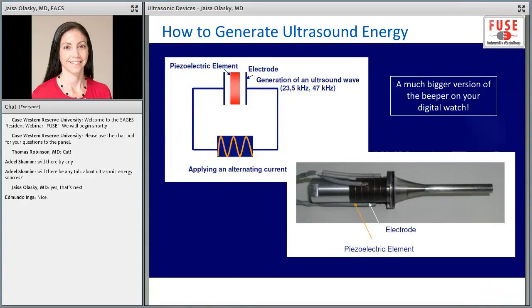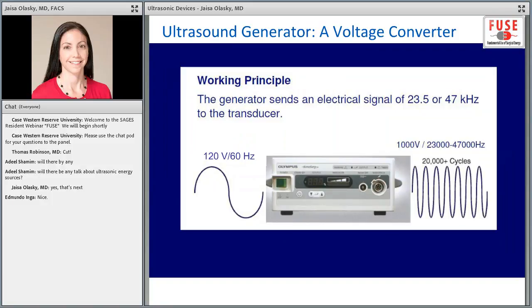So that's one of the major benefits of the ultrasound energy devices. But first, just to describe how this device works, you have to generate the ultrasound energy. Within the handle of the instrument, there's a transducer. Within that, there's a stack of piezoelectrodes, which are positioned between metal cylinders. When this transducer is activated electrically, these piezoelectrodes are excited, and they convert the electric energy going into the handle into mechanical energy that vibrates the cylinders. This creates the ultra-high frequency with the linearly oscillating surface that's then attached to the solid shaft and ultimately the jaws. So that's the basis of how the ultrasound energy is created.